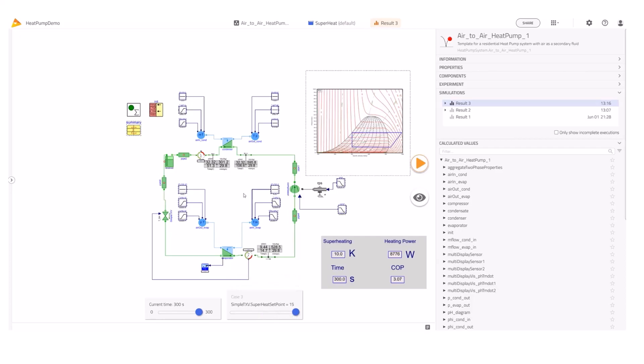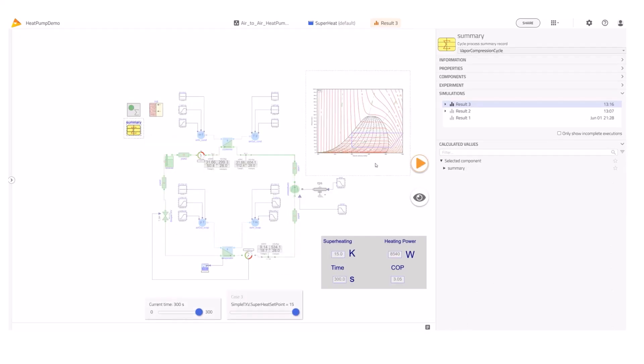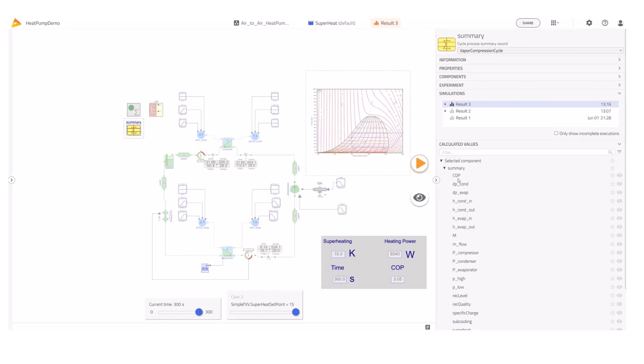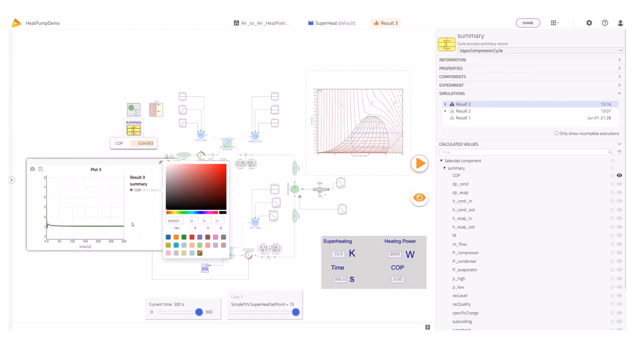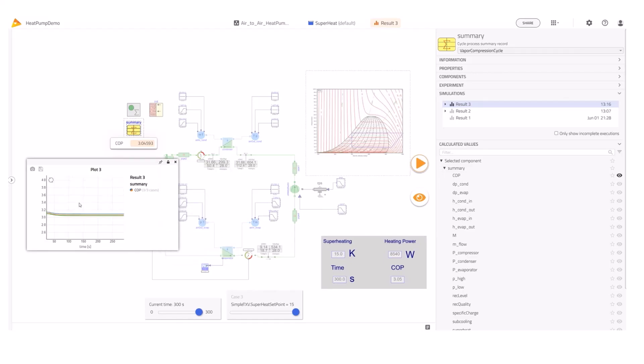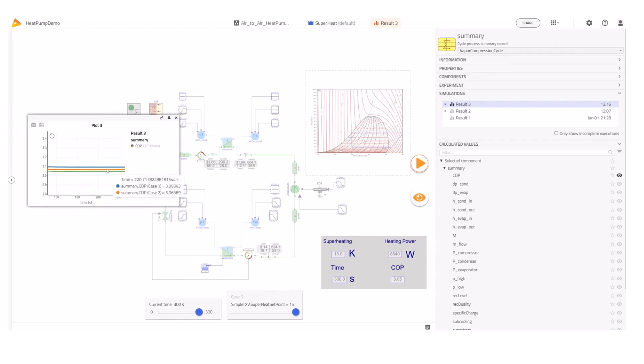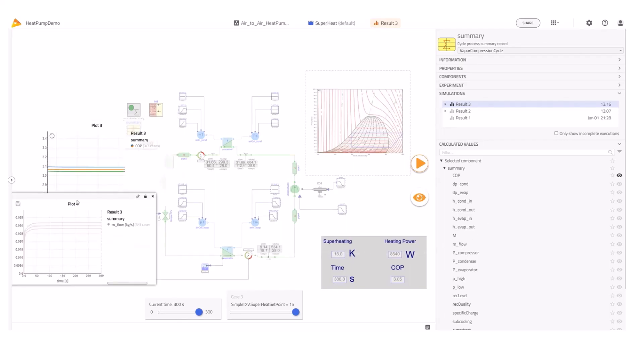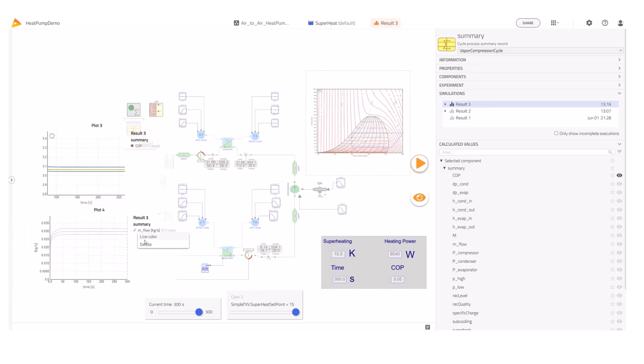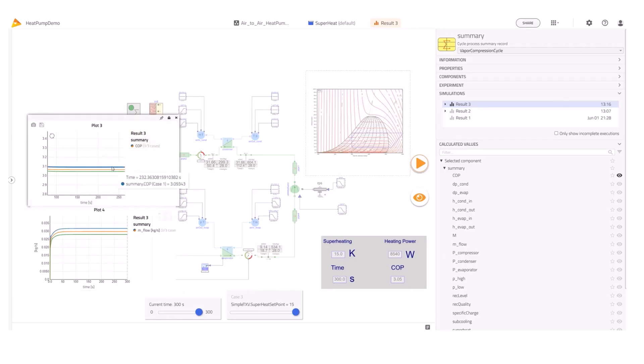Let's explore the results. I click on the summary component and plot the COP. I configure again the line color for the different experiments. The results indicate that the COP is higher at the lower superheating. To understand this effect, I plot the mass flow rate for the three cases. This plot shows that to reach a higher superheating the valve decreases the mass flow, and decreasing the mass flow rate reduces the heat transfer, which explains the lower COP.